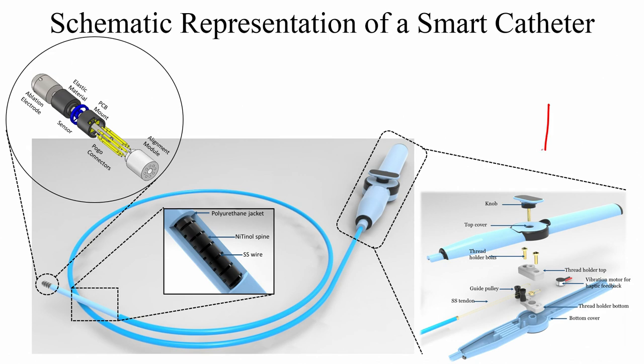From all these experiments, we have thought about how to design an actual catheter that can be used for ablation. This is the maneuvering system: there is a knob, top cover, thread bolts — designed via 3D printing or other manufacturing techniques — a guide pulley, stainless steel tendon, and a vibration motor for haptic feedback. An important gap in current catheters is the absence of haptic feedback: the surgeon can see the force on a display but cannot feel it.